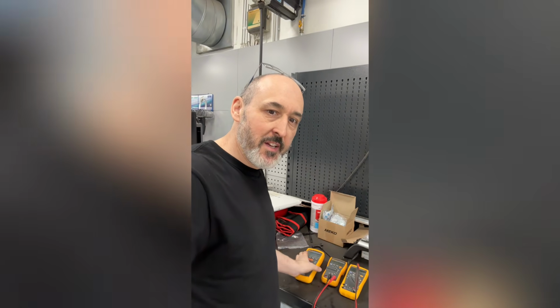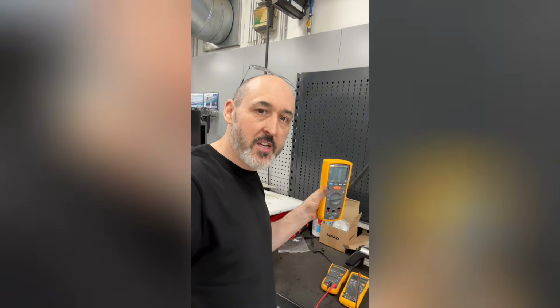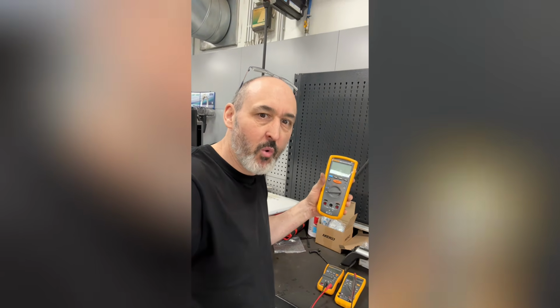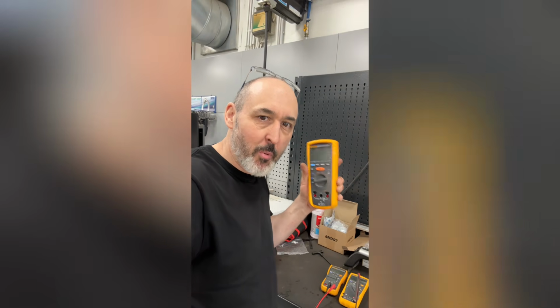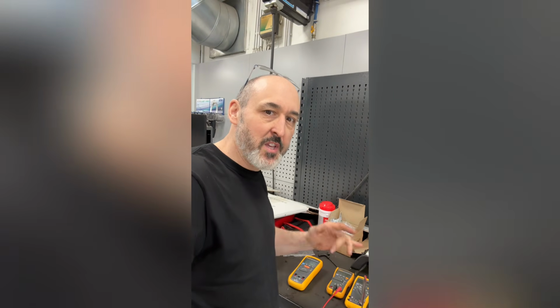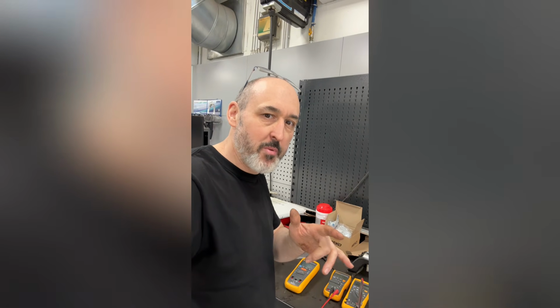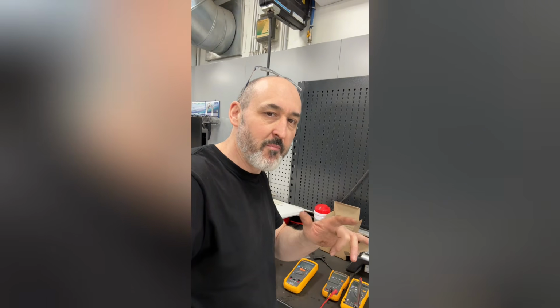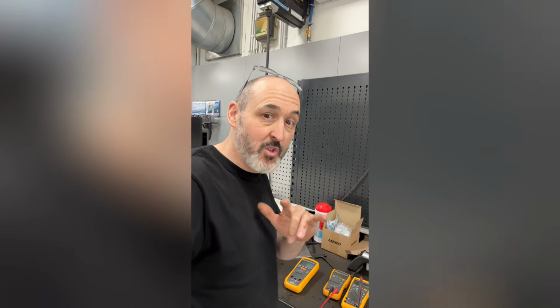That's why you need a proper Fluke meter like this. It's not cheap, about 700 or 800 quid, but it's designed to push 6 volts down so we can get a correct value, because equipotential bonding has got to be very close to zero, hasn't it? You can't have any resistance.